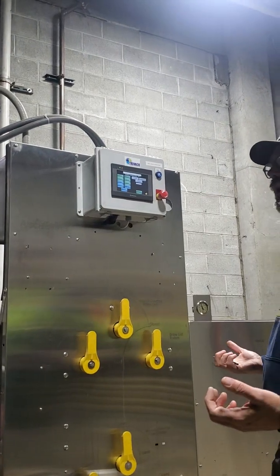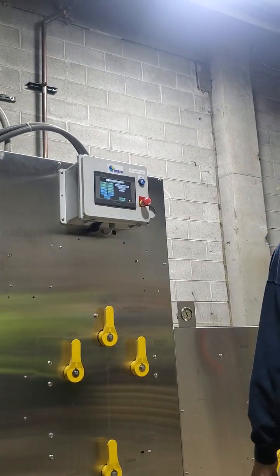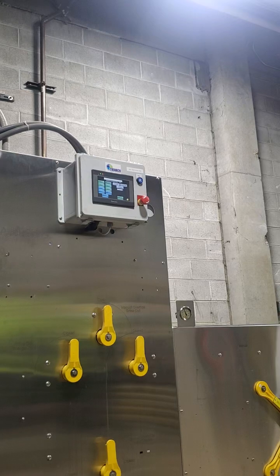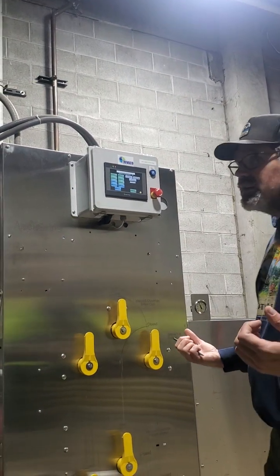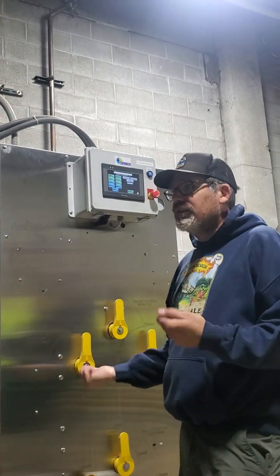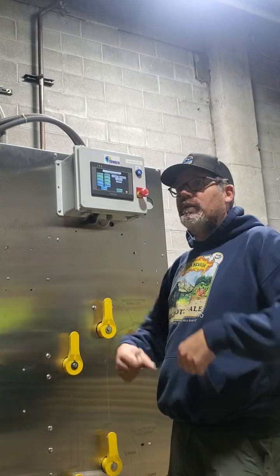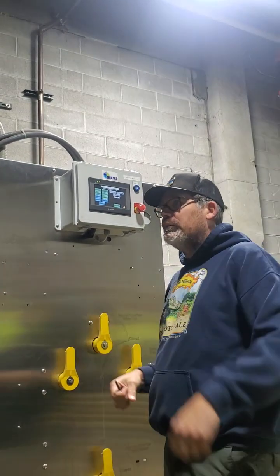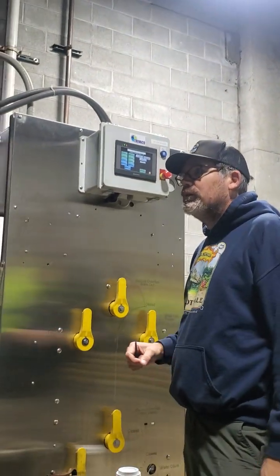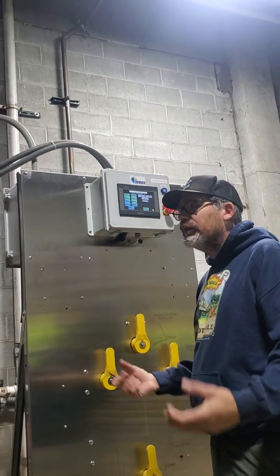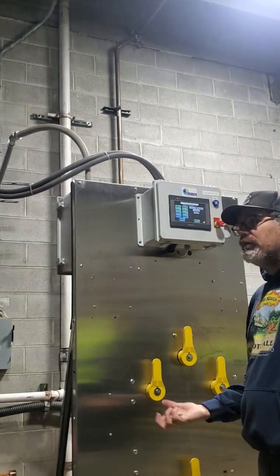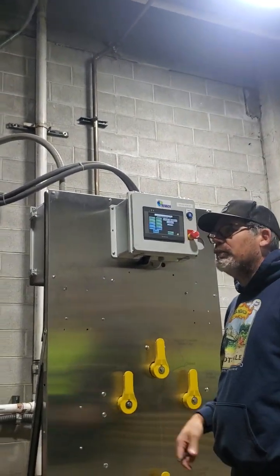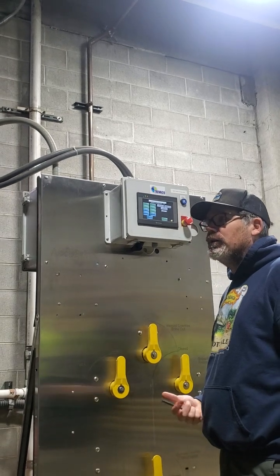The way to do that is capture it coming on the suction side and put a shut-off valve on each side. Then you can isolate it, change it out quick, put it back in, turn the manual valves up and start it back up again. You just want to isolate it so you don't have 10 gallons of product dumping out every time you do it.